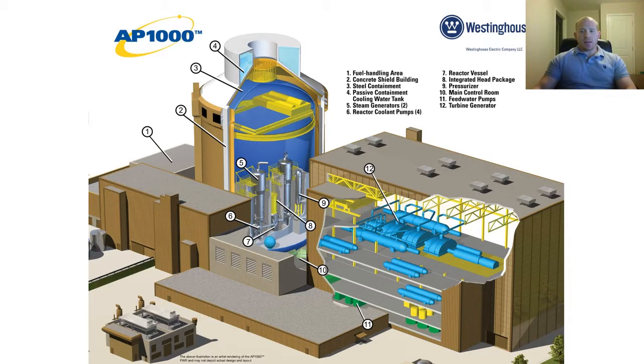The AP1000 can be safely shut down and maintained during a station blackout for 7 days. The advanced passive safety features rely on natural forces such as gravity, natural circulation, condensation, and convection, where the ultimate heat sink is the atmosphere. It has a bunch of power sources. It has a redundant safety-related DC battery bank that supports the safe shutdown for 72 hours. It has 2 redundant 80 kilowatt ancillary diesel generators that provide cooling water to the containment shell and spent fuel pool. The ancillary diesels can run for 4 days with no off-site support.